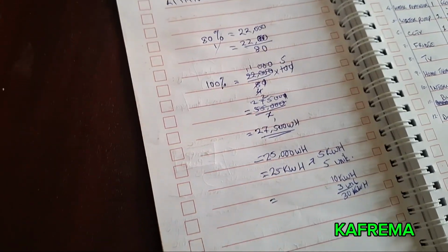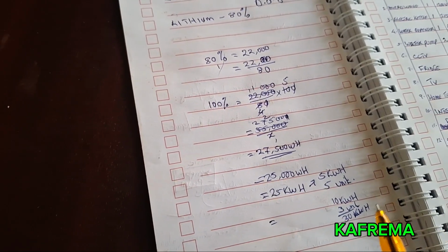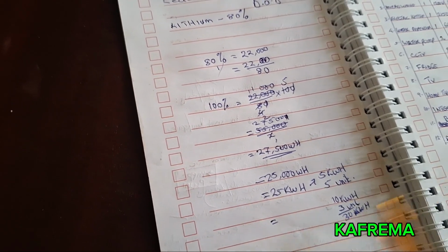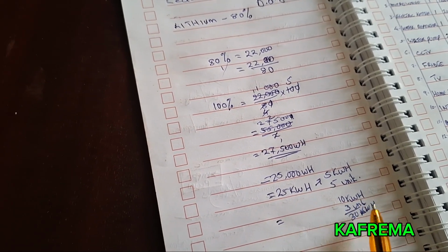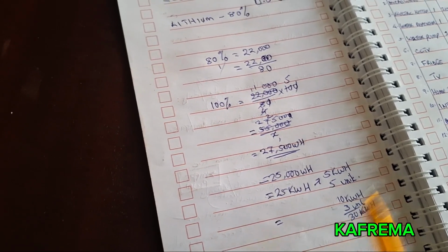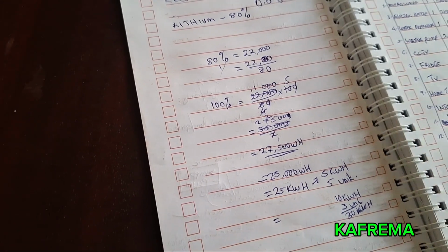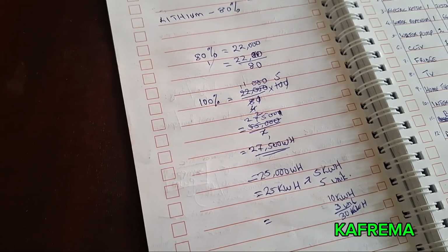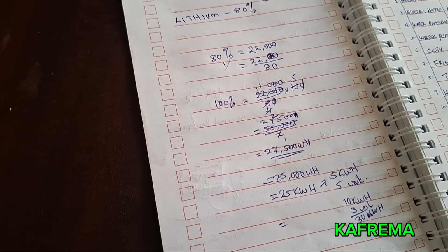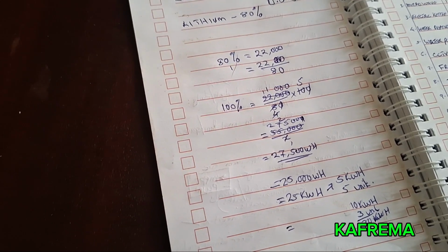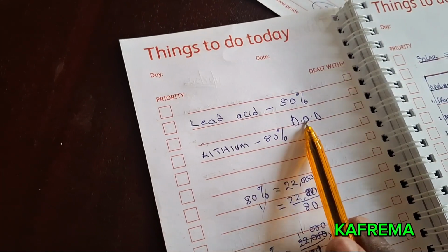So we have seen we require 21 kilowatt hours every day. You can go for the higher, the better. This one will take you 1 day and something, and this one will take you just 1 day. So this is how we determine the amount of battery we require. The most important thing to know is that you cannot discharge your battery to 100%.